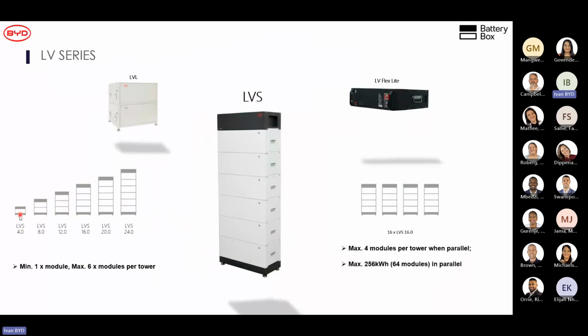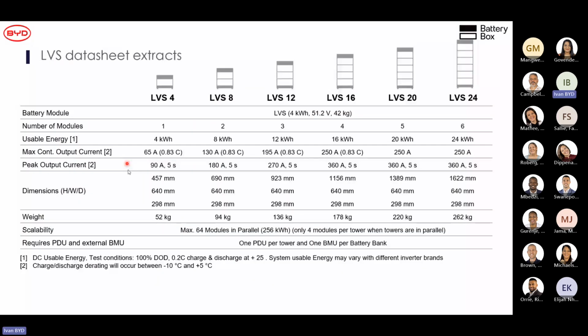And you can start at 4 kilowatt hours, and you can parallel LVS all the way up to 256 kilowatt hours. Here we can see the maximum output current. The 0.8 C battery is continuous, and they do have a peak current for 5 seconds. You can parallel them up to 256 kilowatt hours, which is 64 modules. You do need 1 PDU per tower and 1 BMU per battery bank. So you do need 1 BMU per low voltage battery bank.